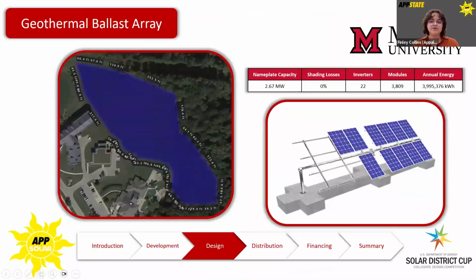The geothermal ballast array is located on the geothermal energy plant well field, which poses certain design restrictions such as requiring a ballasted mounting. However, this allows us to achieve zero shading relatively easily. We chose a single axis tracking mount with a reflective coating designed to reflect light into the back of the panel, further enhancing the bifacial capabilities of this system. This array has a nameplate capacity of 2.6 megawatts with an estimated annual energy production of just under 4 gigawatt hours.